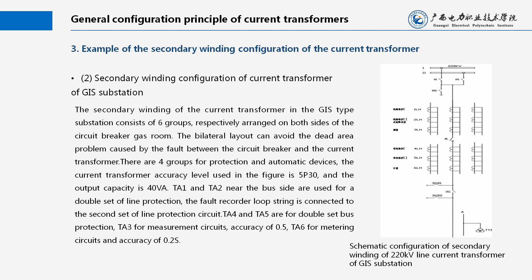Secondary winding configuration of the current transformer of GIS substation: The secondary winding consists of 6 groups, respectively arranged on both sides of the circuit breaker gas room. The bilateral layout can avoid the dead area problem caused by the fault between the circuit breaker and the current transformer. There are four groups for protection and automatic devices. The accuracy level is 5P30 and the output capacity is 40VA. TA1 and TA2 near the bus side are used for double set of line protection, TA4 and TA5 are for double set bus protection, TA3 for measurement circuits with accuracy of 0.5, and TA6 for metering circuits with accuracy of 0.2S.